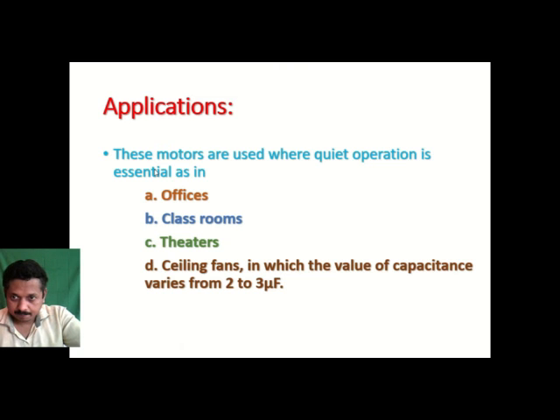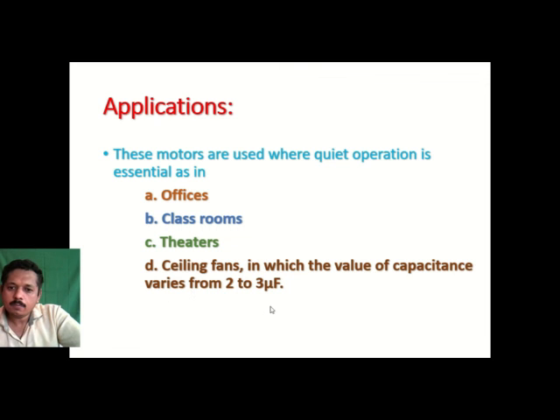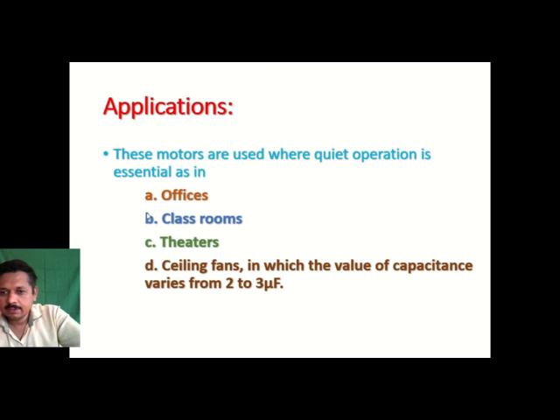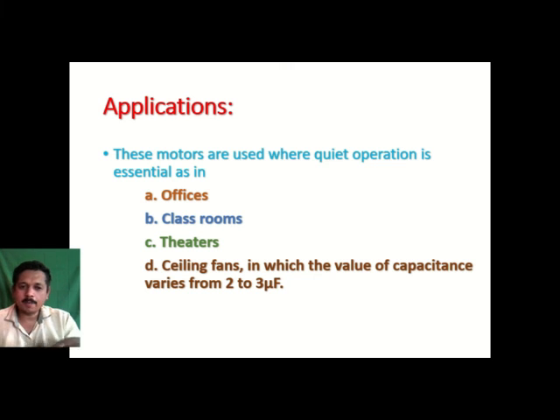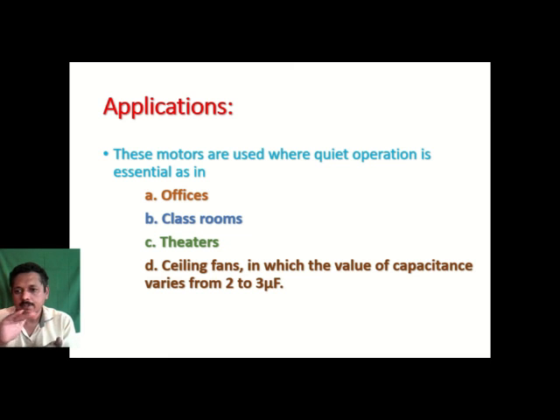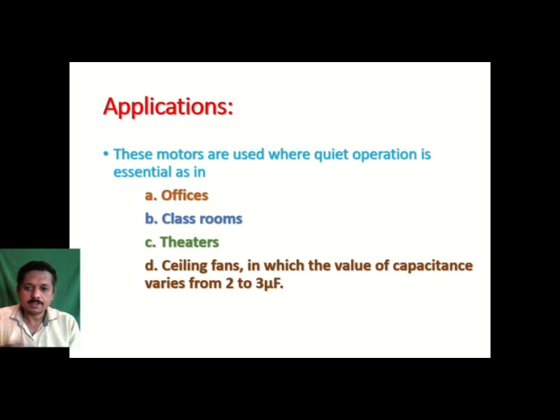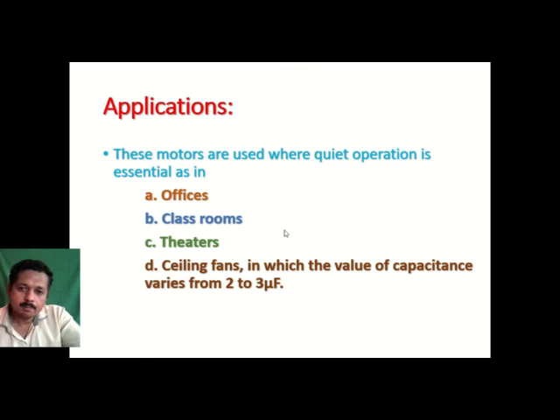These motors are used where quiet operation is essential: offices, classrooms, theatres, and ceiling fans, where the capacitor value ranges from 2 to 3 microfarads. They can also be used for refrigerators and compressors. One important limitation is that the starting torque is moderate — not as high as the capacitor start motor or capacitor start and run motor. Its starting torque is less than those two types, but its operation is very smooth, which is why it can be used with a small capacitor of 2 to 3 microfarads.